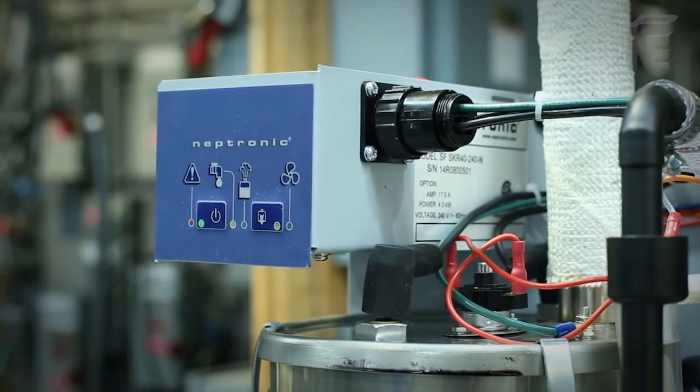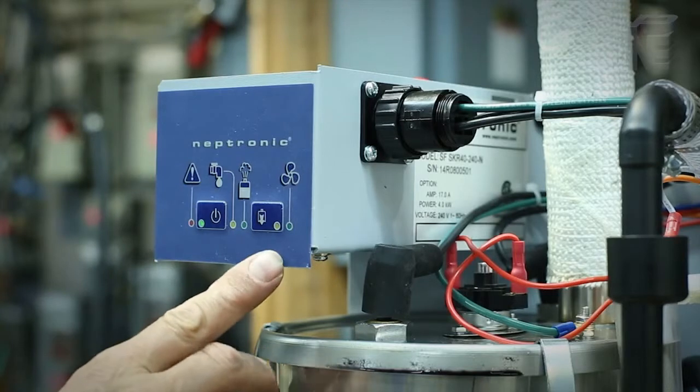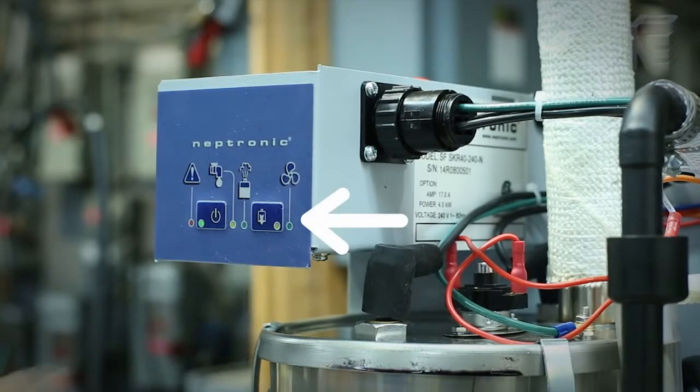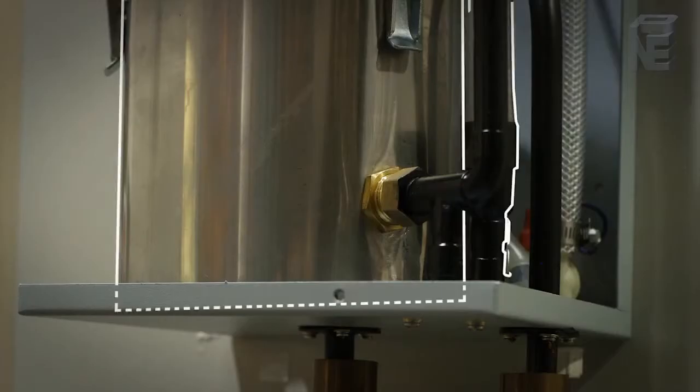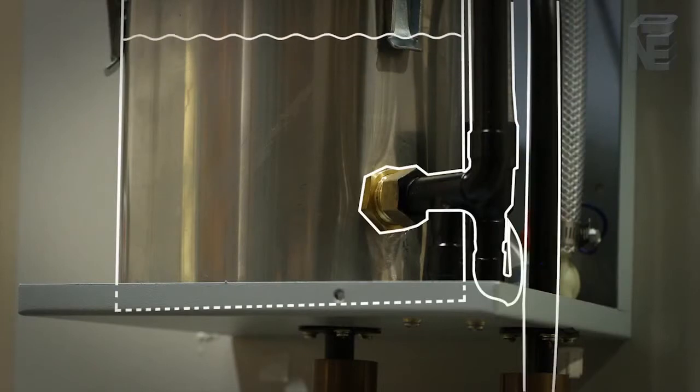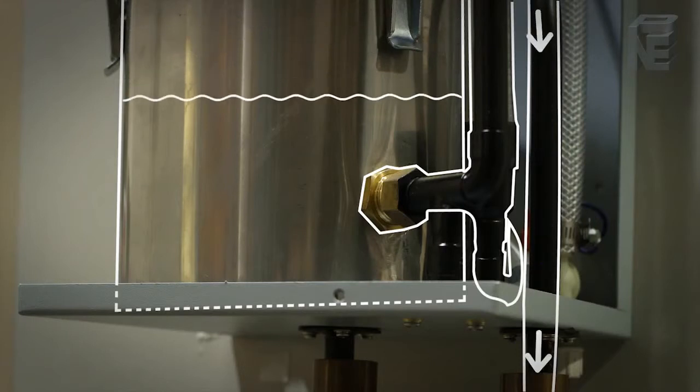With the power still on, drain the boiling chamber by pressing the drain down button on the front panel. The humidifier will fill with water just about to the brim of the chamber, thus initiating a siphon which will empty the cylinder of water.